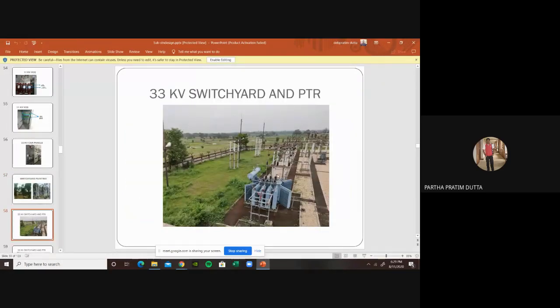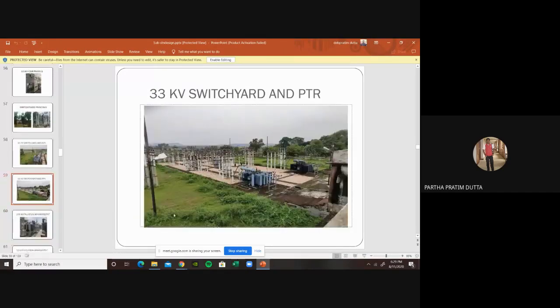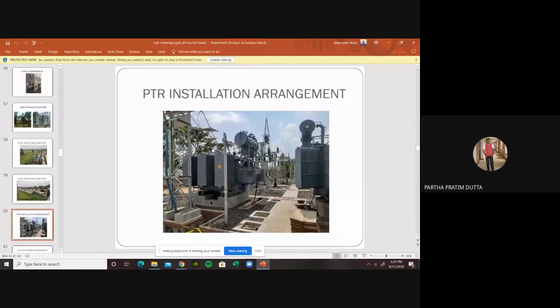There is a panoramic view of the substation. This is also another panoramic view of the substation. This is the PTR installation arrangement. These are the plinths. You see, we usually use the same plinth for a 6.3 MVA transformer and a 10 MVA transformer. It is 3125 by 3125 millimeter, and the legs are 0.6 meter each, and it is placed over it for 6.3 and 10 MVA, the same plinth size.